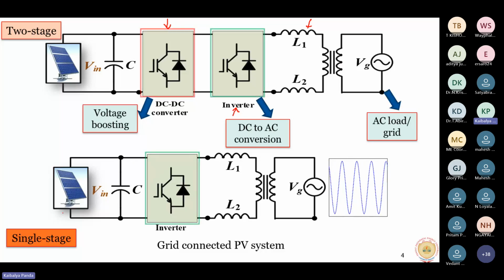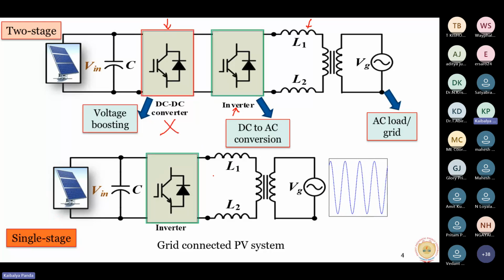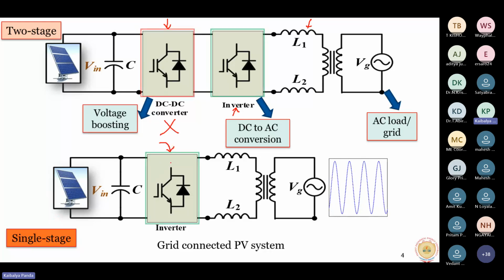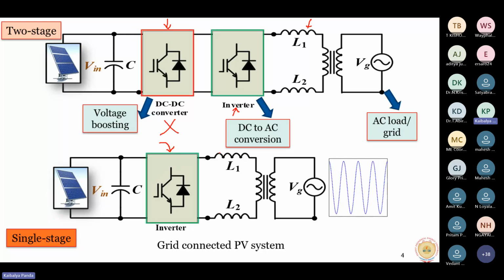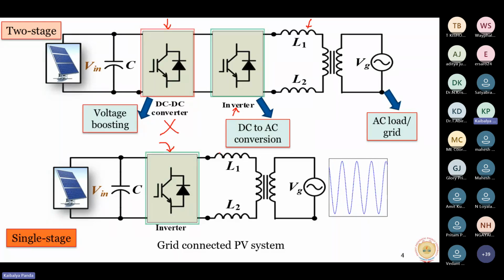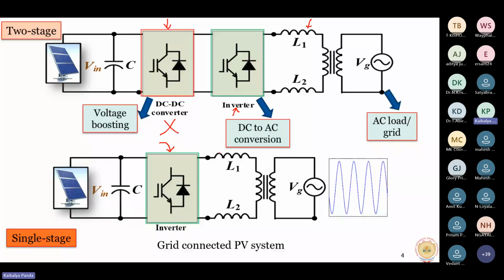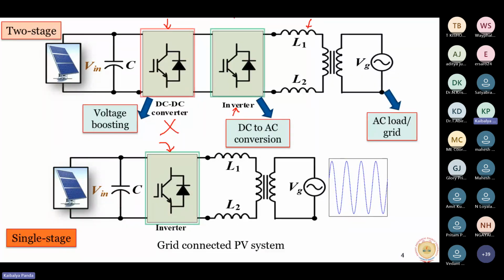Now there are also single stage systems possible where these DC-DC converters can be completely avoided. If you want to avoid a DC-DC converter, the inverter should be capable of boosting the voltage. If you use a general conventional inverter, either single phase or three phase, without a DC-DC boost converter, the inverter itself must be capable of boosting the voltage.